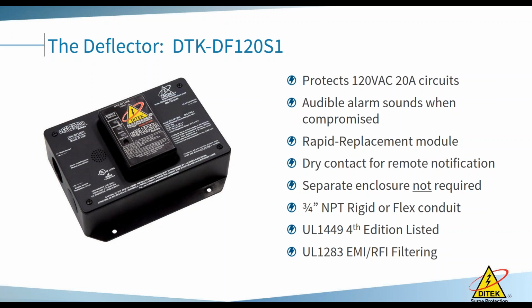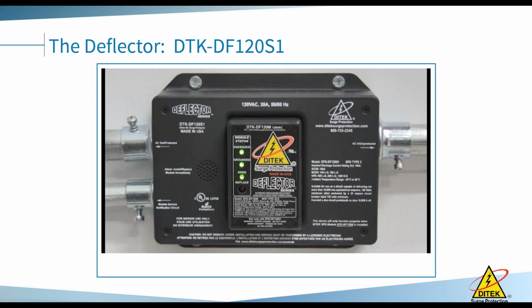I can tell you from experience, customers are never unhappy when you're out there to replace a surge protector. That's a good call to have to replace one of my widgets versus going out there and saying, ooh, I'm sorry, we got to replace 5 or 6 boards. This isn't the day of 15 years ago where you had one addressable panel at the main spot and then everything was cheap conventional panels reporting back to it. Nowadays, majority of places I go, they're all addressable panels. And add in voice evac, mass notification and things like this, these printed circuit boards are in the thousands upon thousands of dollars. This is nothing to offer a protector that's really low cost, but it'll let you know if it self-sacrifices so you can go out there and replace your protector versus replacing the board.